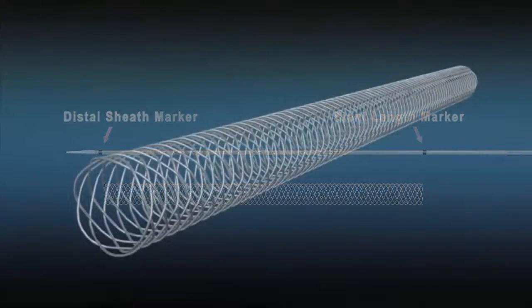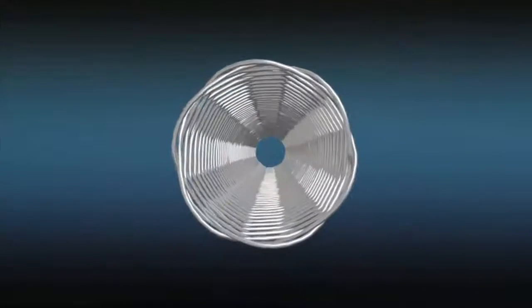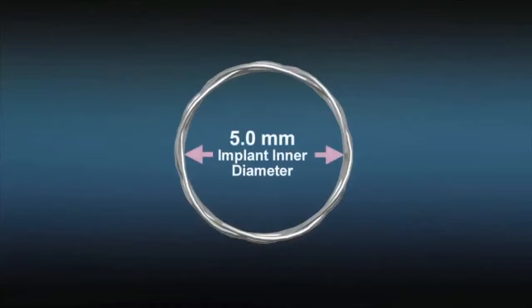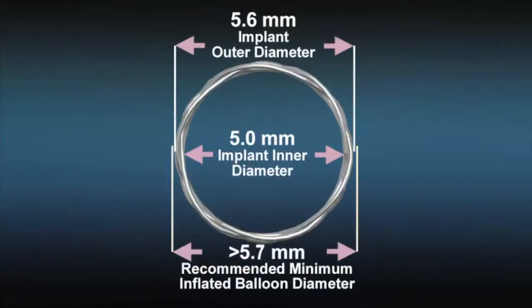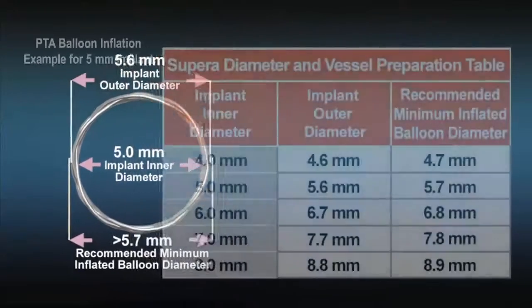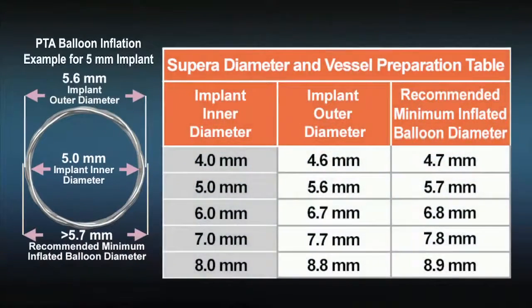The label diameter of Supera is based on its inner diameter. Inflating a PTA balloon prior to Supera deployment will prepare the vessel to accept the implant's outer diameter. This table displays the recommended minimum balloon inflation diameter for each corresponding labeled implant diameter.